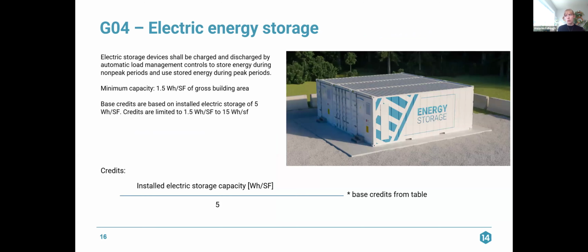Electric energy storage. Electric storage devices shall be charged and discharged by automatic load management controls to store energy during non-peak periods and use stored energy during peak periods. So again, this is a load shift, not a load shed, right? We store up the batteries, we put a bunch of electricity into the batteries, and then use that to reduce our peak rather than business as usual at nighttime. We're going to increase the energy use at night a little bit and offset that peak.